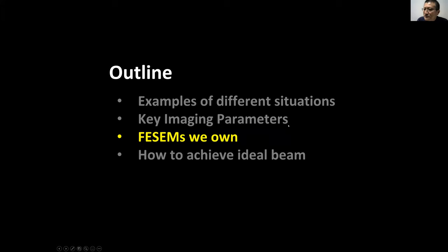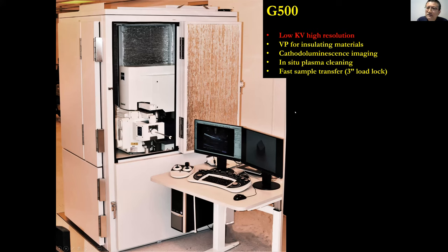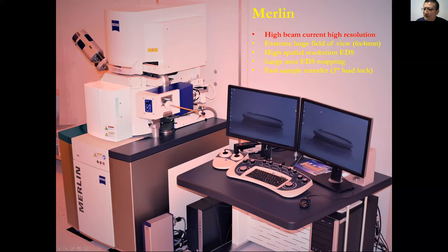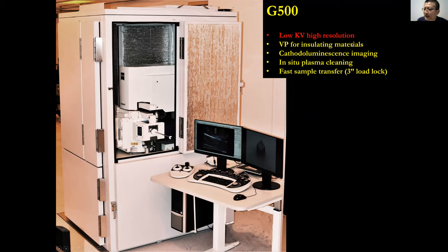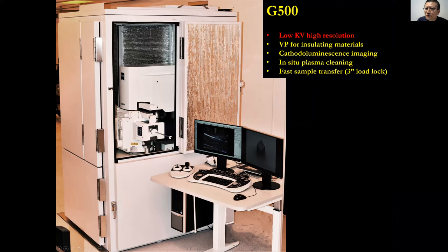Next we talk about the SEMs we have in our clean room — two SEMs: Merlin and G500, both made by Zeiss, both top-of-the-line. For most samples they do similar jobs, but they differ: Merlin can do high beam current at high resolution. G500 can do low kV at high resolution. EDS requires high beam current, so use Merlin. For 2D materials requiring low kV, G500 is better. You need to pick the right SEM for your sample.